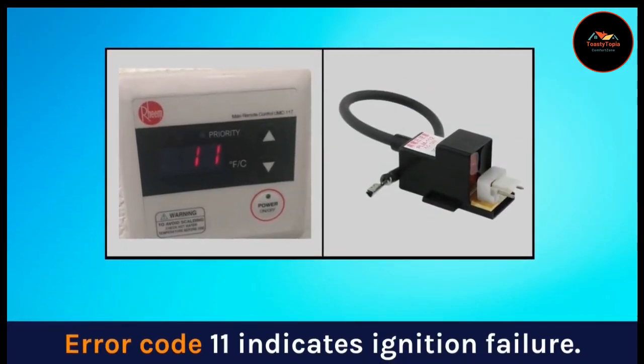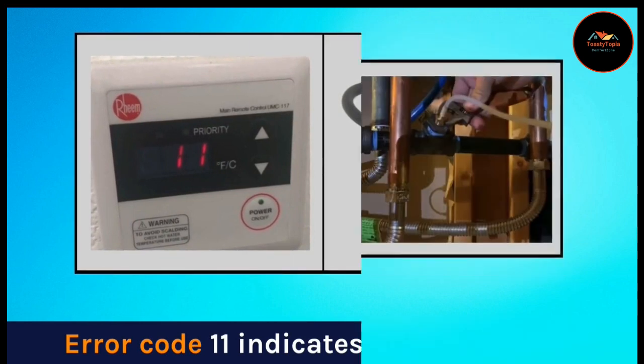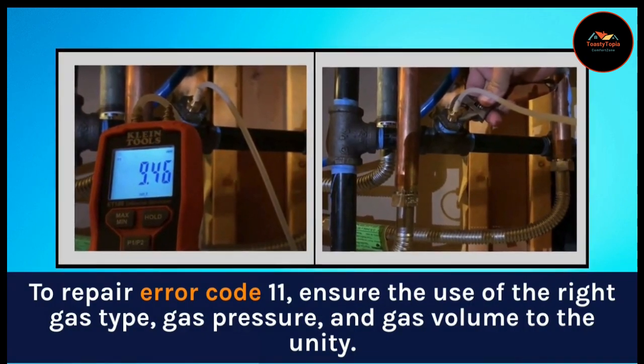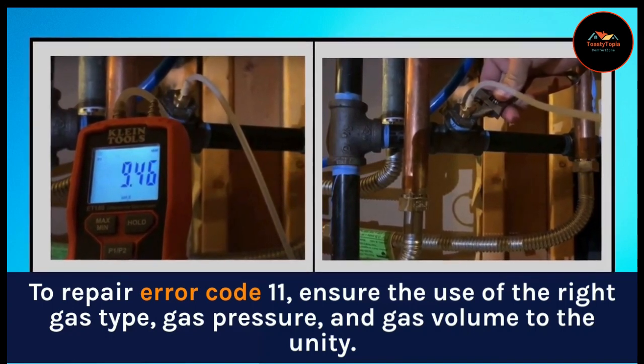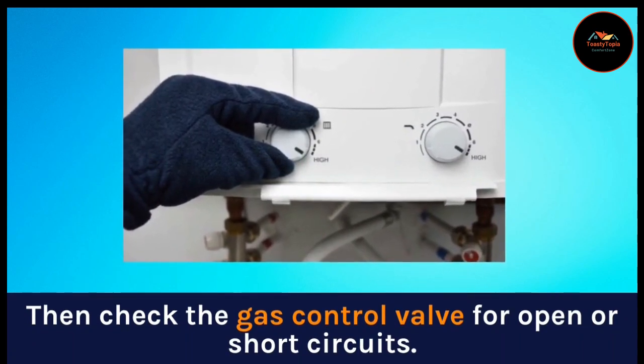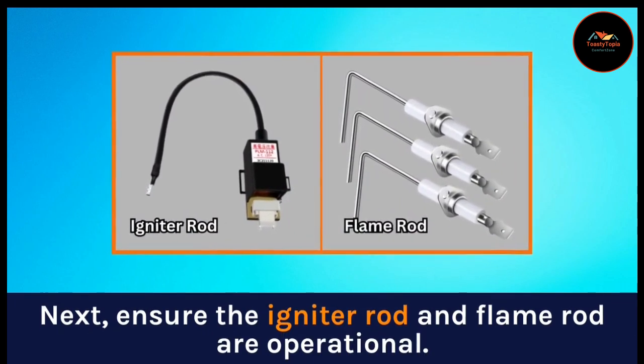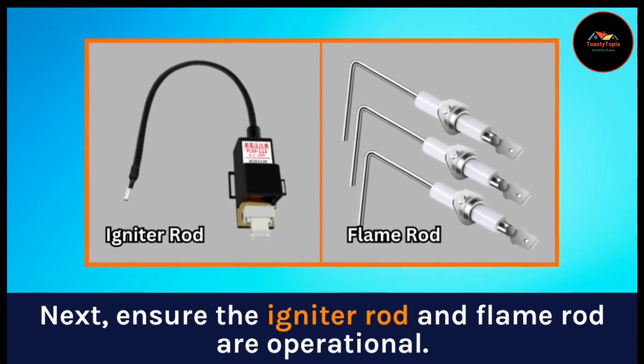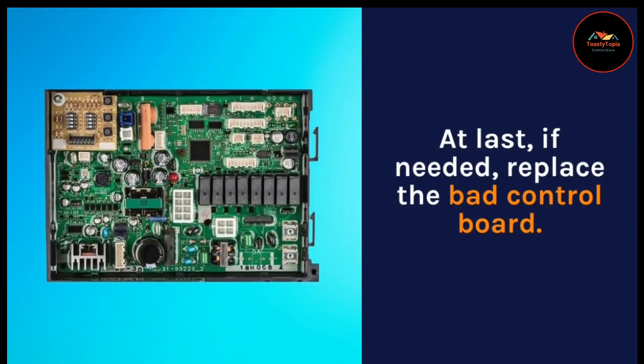Error code 11 indicates ignition failure. To repair error code 11, ensure the use of the right gas type, gas pressure, and gas volume to the unit. Then check the gas control valve for open or short circuits. Next, ensure the igniter rod and flame rod are operational. If needed, replace the bad control board.